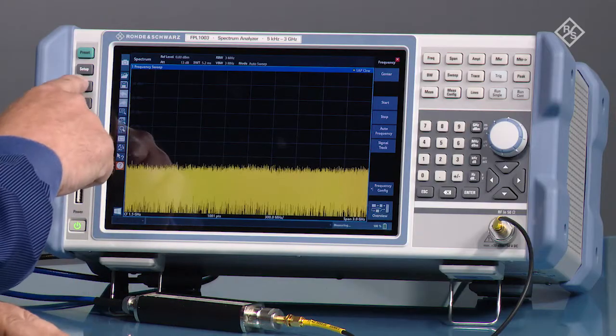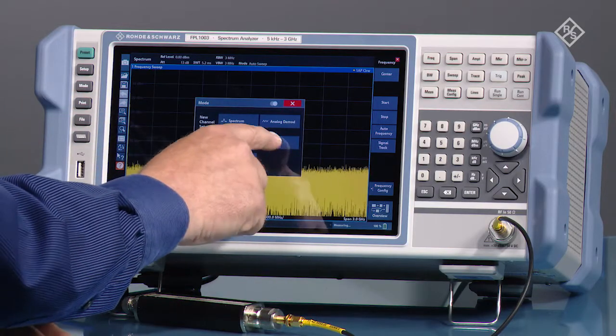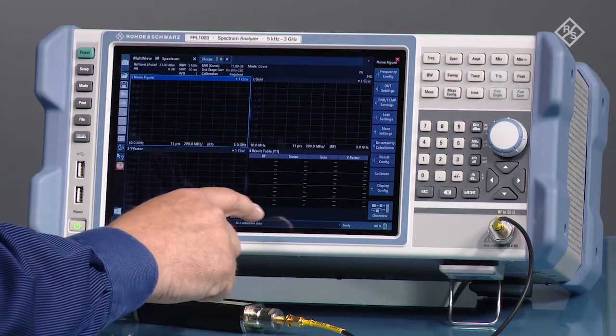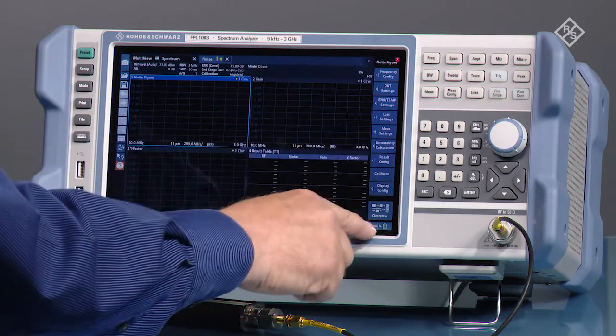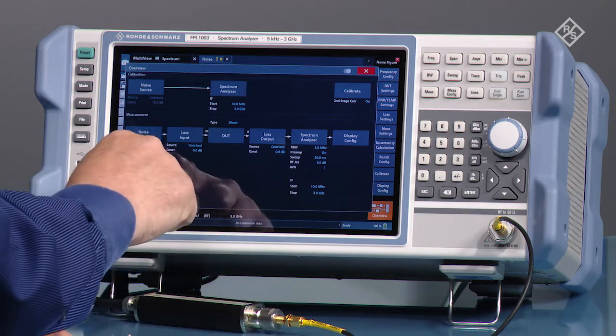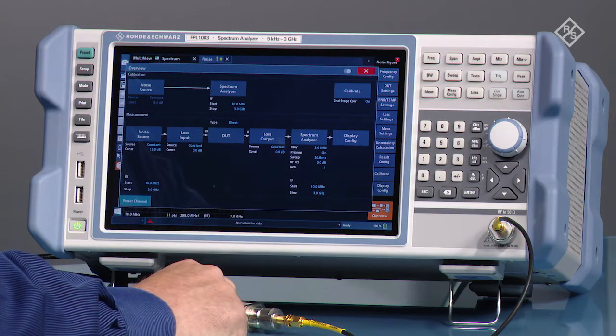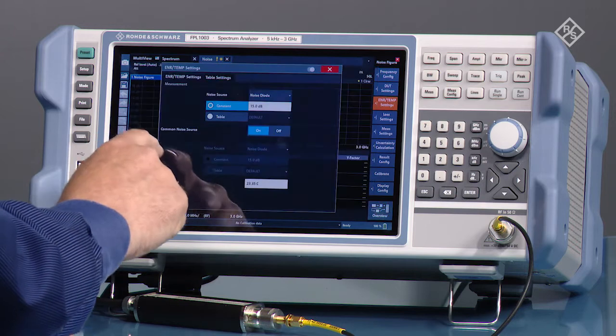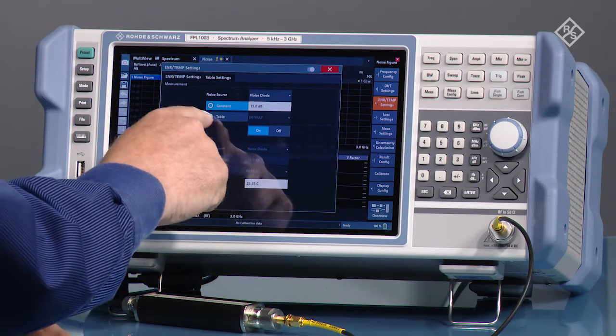We're going to start by selecting mode and open up the noise figure option. Here we have an overview button where we can step through all of the steps to set up the noise figure measurement. We're going to start under noise source and create a table.